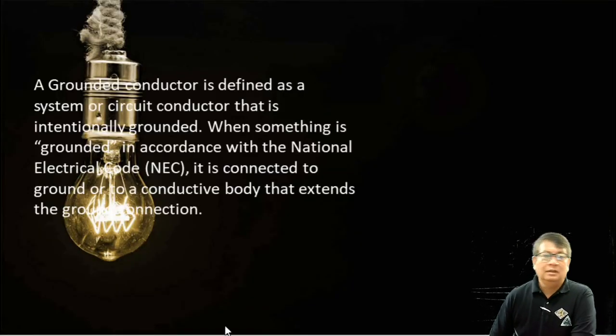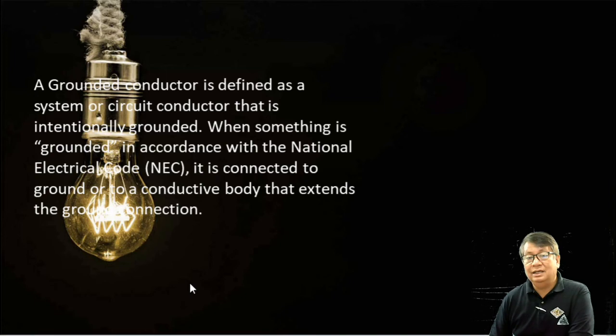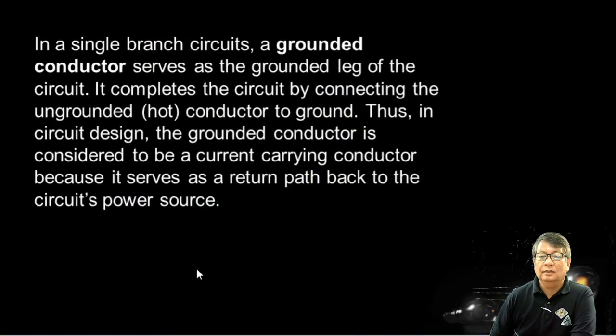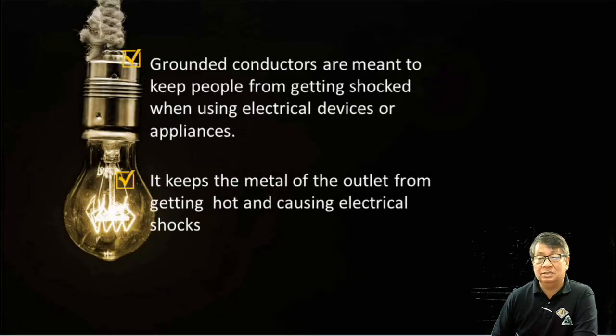So what is a grounded conductor? Basically, according to the definition, a grounded conductor is a system or circuit conductor that is intentionally grounded. When something is grounded in accordance with the National Electrical Code, it's connected to ground or to a conductive body that extends the ground connection. In a single branch circuit, the grounded conductor serves as the grounded leg of the circuit. It completes the circuit by connecting to the ungrounded conductor. Thus, in circuit design, the grounded conductor is considered a current-carrying conductor because it serves as a return path back to the circuit's power source. I hope that you had been practicing this one. Grounded conductors are meant to keep people from getting shocked when using electrical devices or appliances. It keeps the metal of the outlet from getting hot and causing electrical shocks.